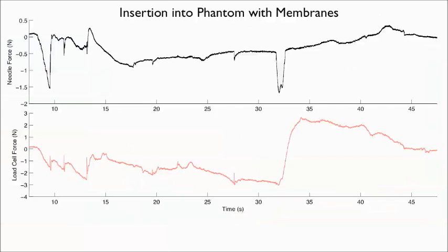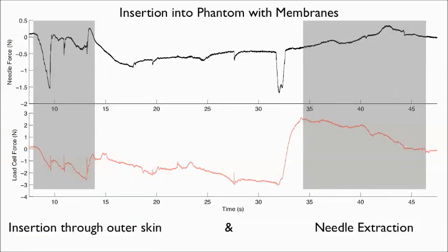A comparison of force profiles shows piercing of the 3-layer skin during insertion. During extraction, the load cell sees exaggerated frictional forces while the needle tip sensor truly measures forces at its tip.